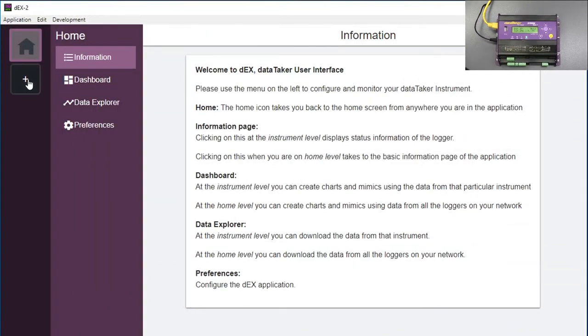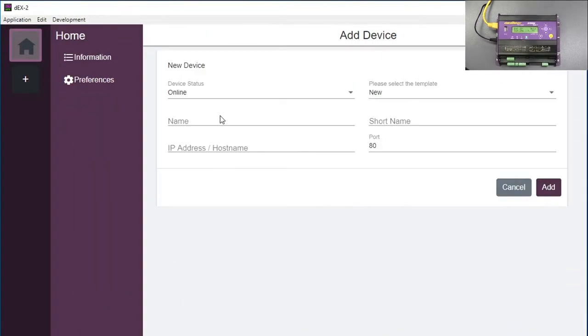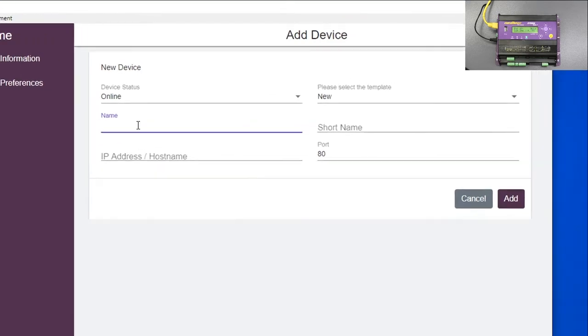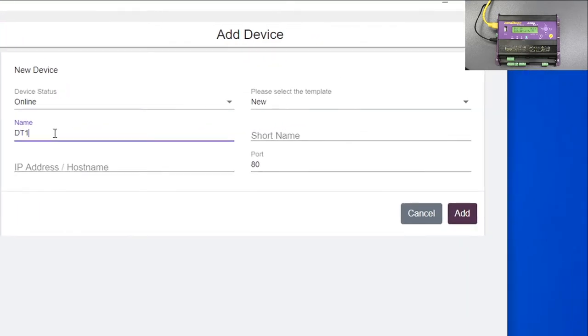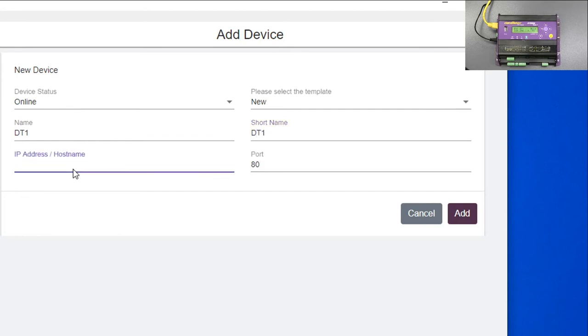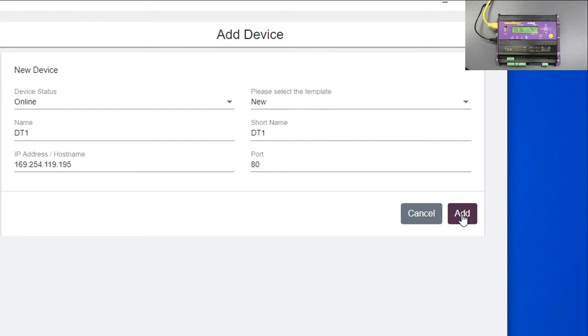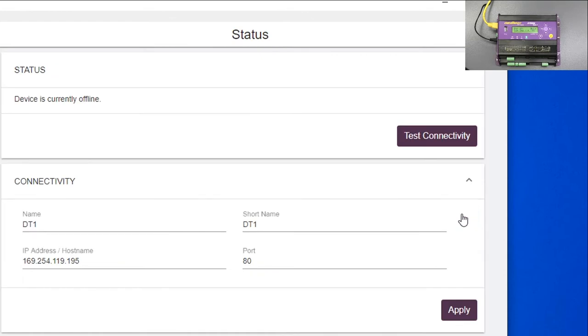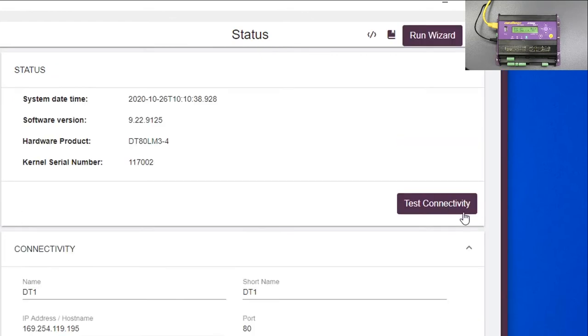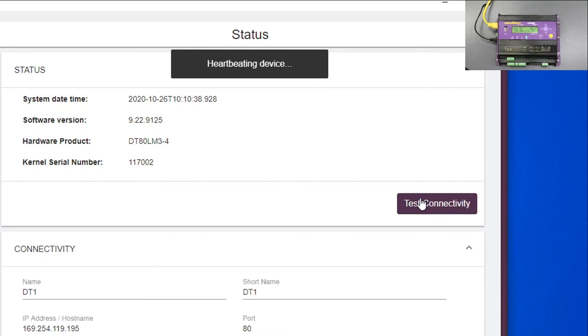What I have to do is I have to come over here. I have to add a logger. So I'm going to call name, this is DT1 and our short name will be DT1. I need to put the IP address in, which in this case is 169.254.119.195. Now we add that. Now we test. This is now brought up. It's found the logger. We can test the connectivity. It's fine. That's the serial number of the logger there. So it's all fine, it's all running.